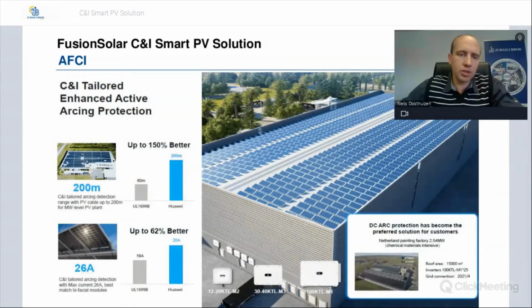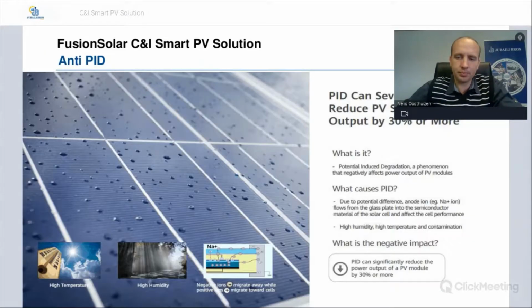In this next slide, we're comparing how the Huawei AI AFCI solution is better than the standards. According to the arcing standards, arcing should only be detected up to 80 meters, but with the Huawei solution, it can be detected up to 200 meters, which means it's more than 150% better than the standards. The current standards for arcing also only require detection up to 16 amps. The Huawei can do detection up to 26 amps.